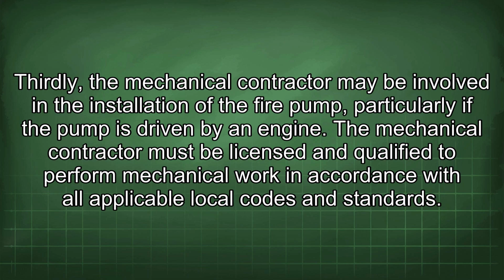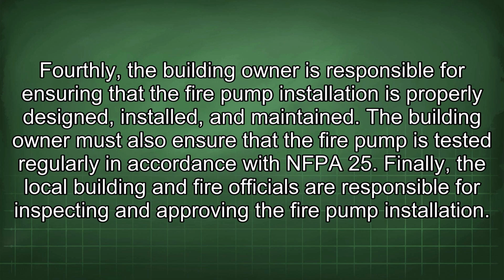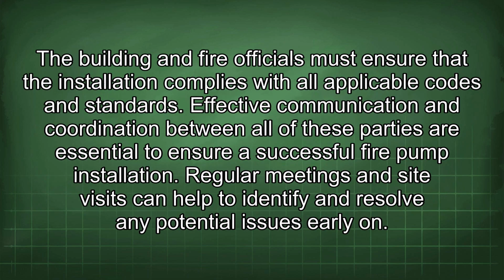Fourthly, the building owner is responsible for ensuring that the fire pump installation is properly designed, installed, and maintained. The building owner must also ensure that the fire pump is tested regularly in accordance with NFPA 25. Finally, the local building and fire officials are responsible for inspecting and approving the fire pump installation. The building and fire officials must ensure that the installation complies with all applicable codes and standards. Effective communication and coordination between all of these parties are essential to ensure a successful fire pump installation.